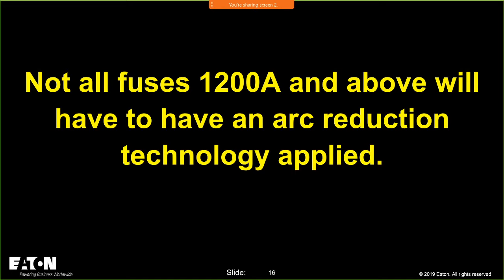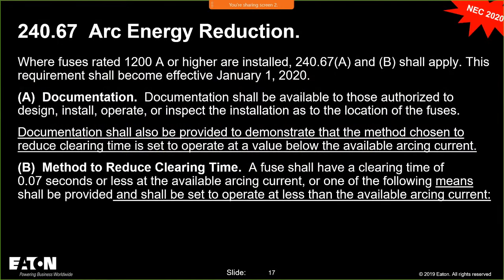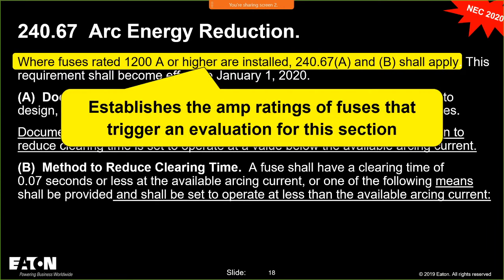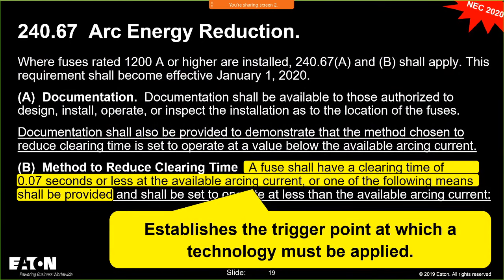All right. So not all fuses 1200 amps and above are going to have an arc reduction technology applied. And I think I explained why, because some of these arcing currents are going to clear faster than 0.07 seconds. Now let's take a look at this language. So these are all the trigger points: 1200 amps and higher installed. That's one of the trigger points. If you have a fuse that's 1200 amps and higher, you know you've got to go look at 240.67. And if you calculate the arcing current and it has a clearing time greater than 0.07 seconds, that is the second trigger point that's going to get you into whether or not you need an arc reduction technology.